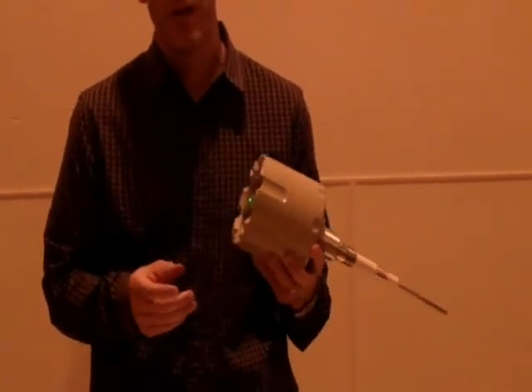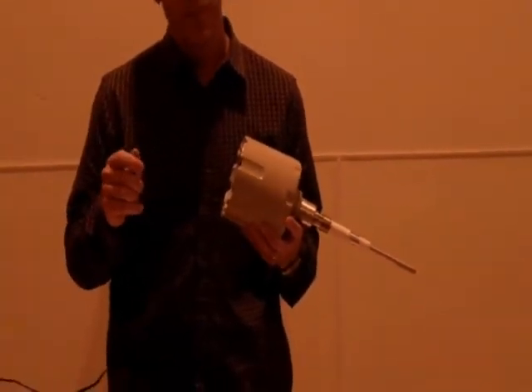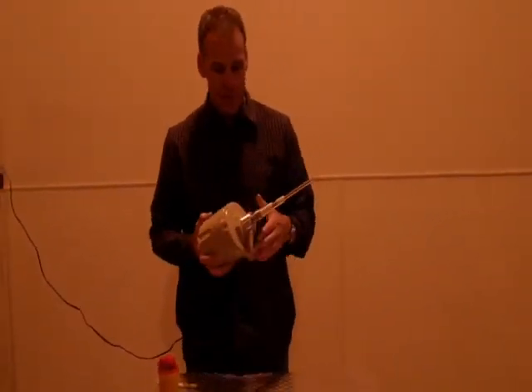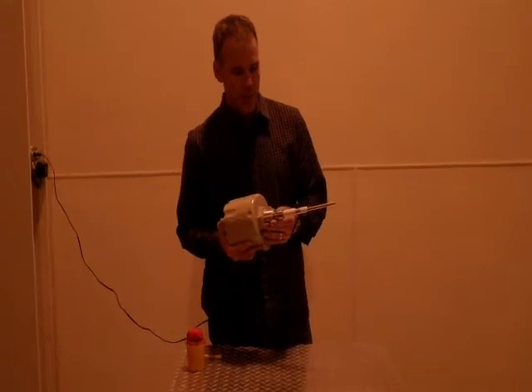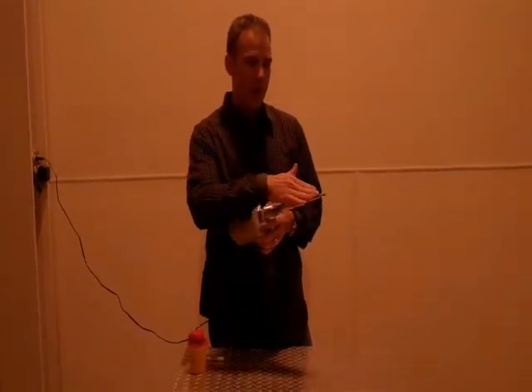There are many controls out there that have to use a magnetic key, a push button, an individual key, or a remote display to reset your unit. A capacitance probe in general is going to have a probe that comes out — it's completely solid state — and the control is going to send a sine wave out through the end of the probe.